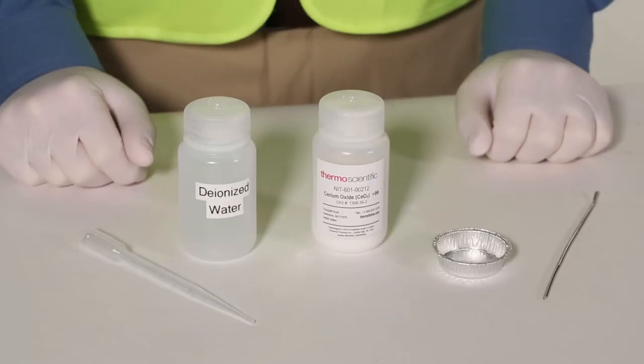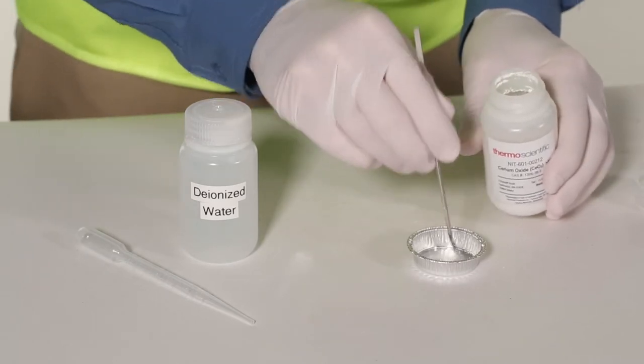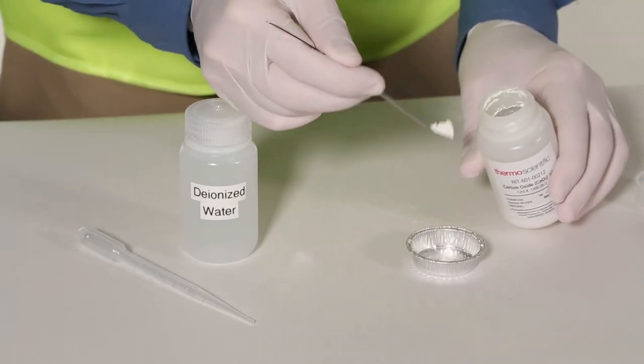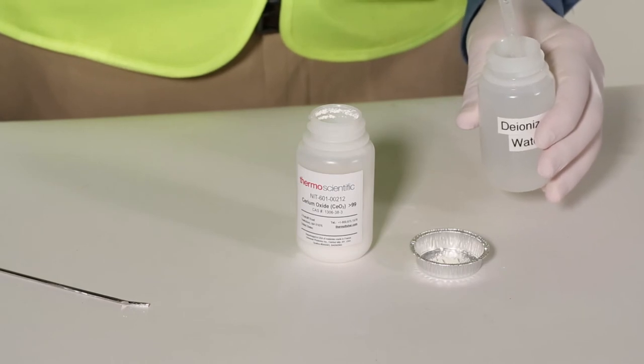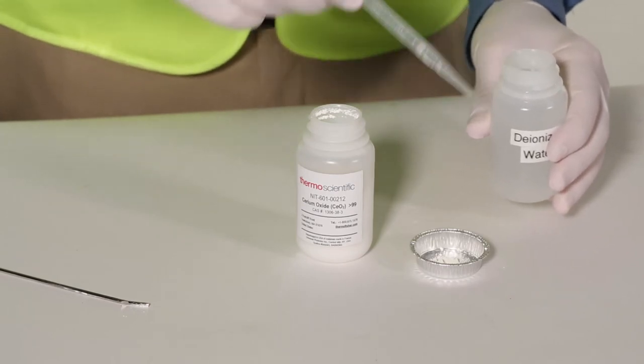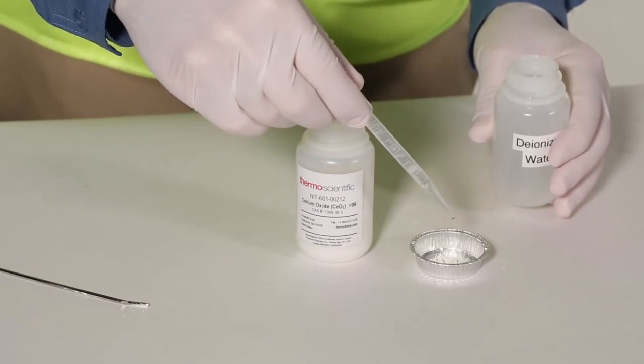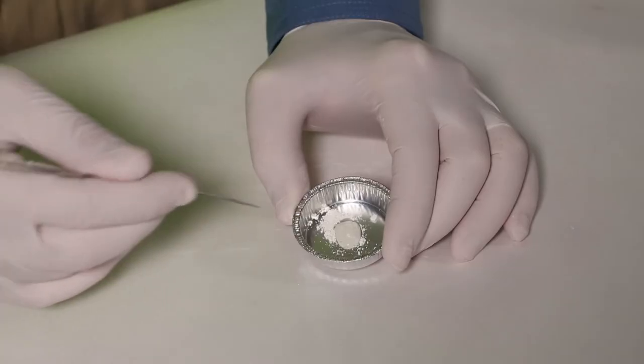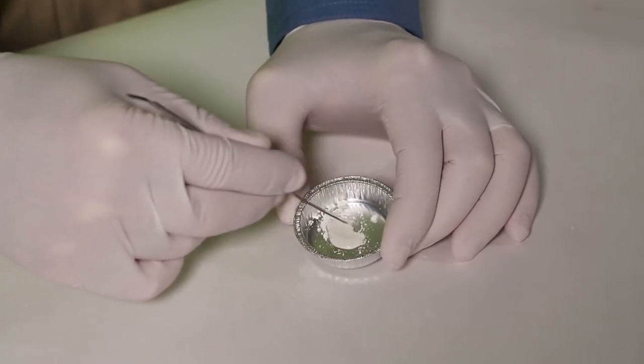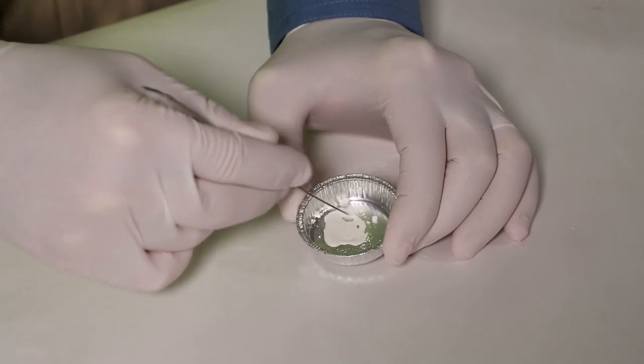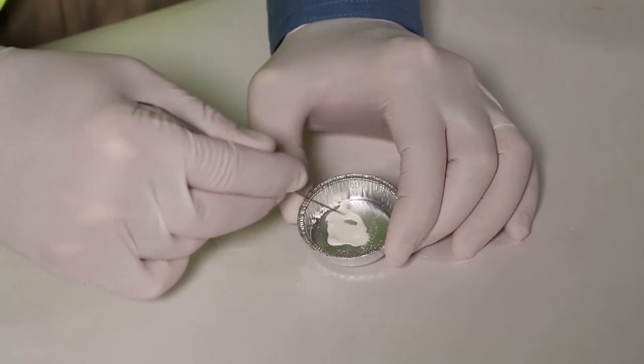Next, an opaline cleaning mixture will need to be prepared. Using the mixing spatula, place two to three scoops of opaline powder in the mixing tray. Use the pipette to transfer deionized or distilled water. Place four to six drops of water in the mixing tray with the opaline powder. Use the mixing spatula to blend both ingredients together until they form a pasty consistency, similar to that of toothpaste.